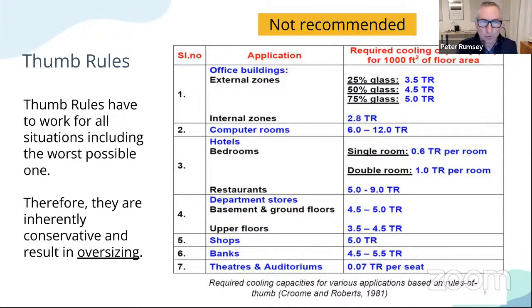So there are many thumb rules. The problem is I don't recommend them because they often result in oversizing. A thumb rule is set up to work every time, in every building, including the worst buildings from a cooling perspective. So thumb rules, like 99% of the time, result in equipment that is oversized and too big, which wastes money in construction. And equipment is also less efficient when oversized. So I don't like thumb rules.